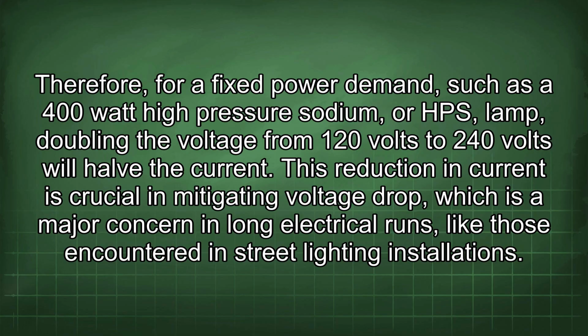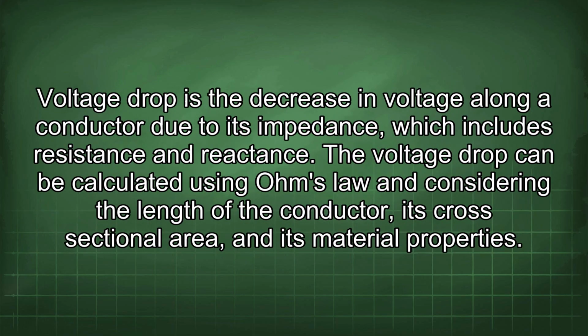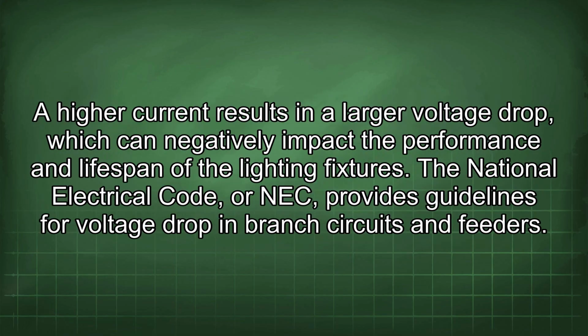This reduction in current is crucial in mitigating voltage drop, which is a major concern in long electrical runs like those encountered in street lighting installations. Voltage drop is the decrease in voltage along a conductor due to its impedance, which includes resistance and reactance. The voltage drop can be calculated using Ohm's law and considering the length of the conductor, its cross-sectional area, and its material properties.